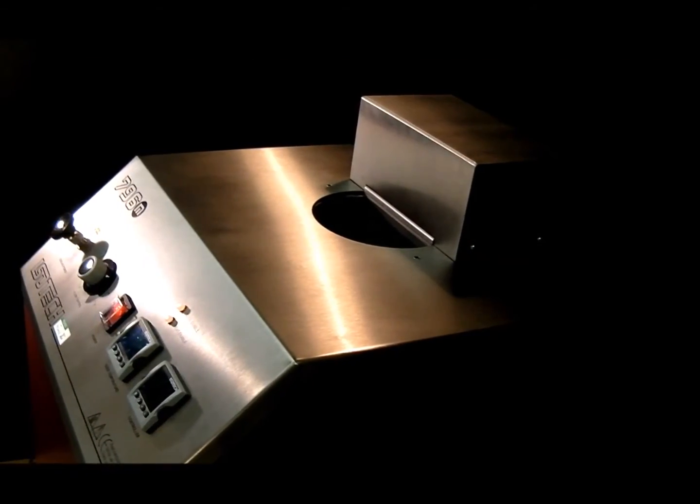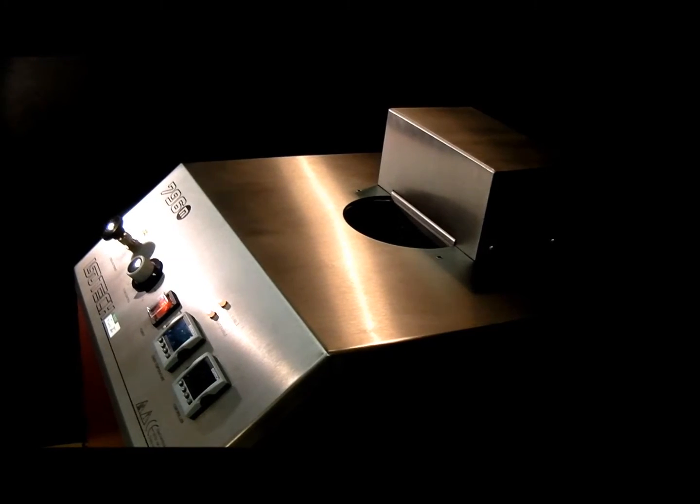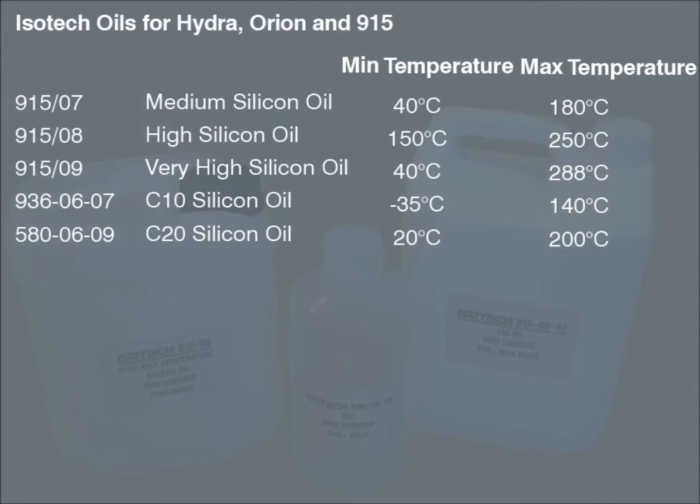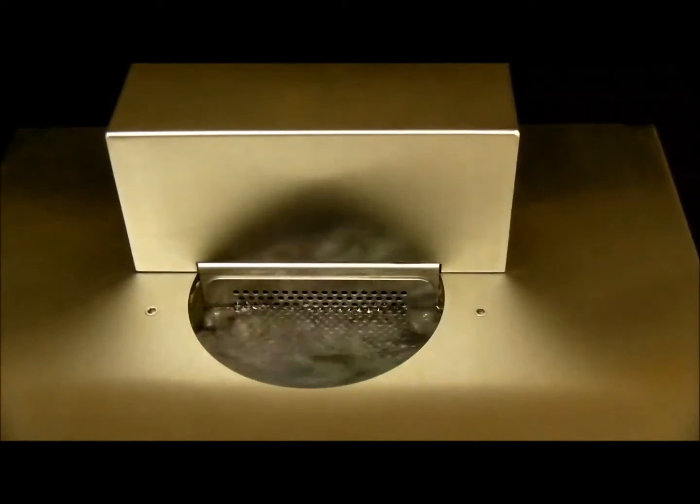Isotech baths like the Orion have always been designed for thermometer calibration, setting the standard for immersion depth versus filling costs. The Orion requires just 8.5 litres of fluid, which provides significant cost savings when compared to other larger volume baths.